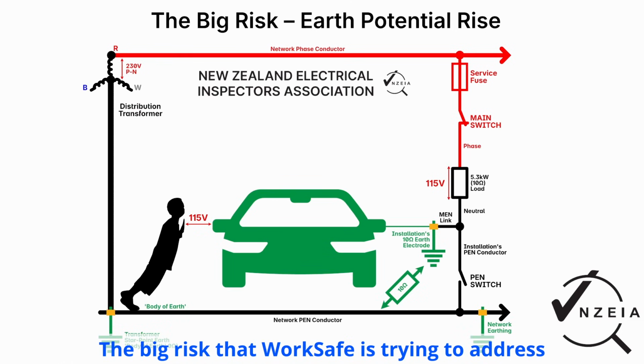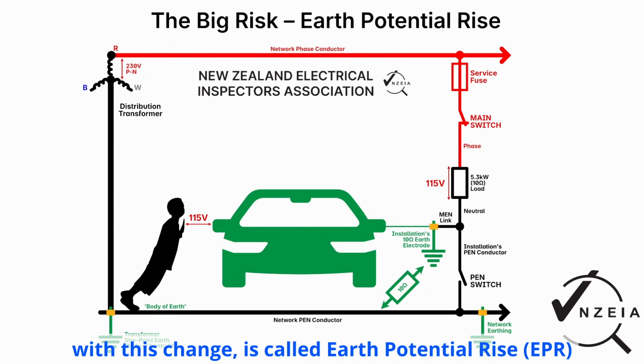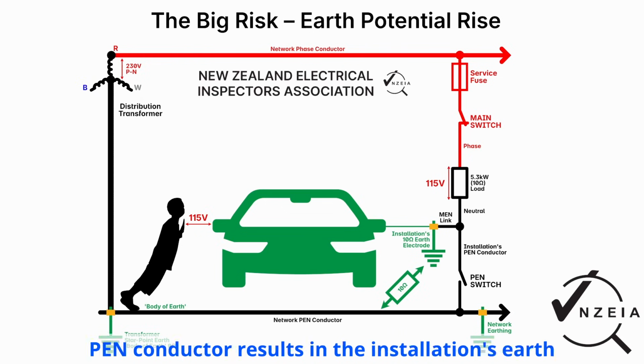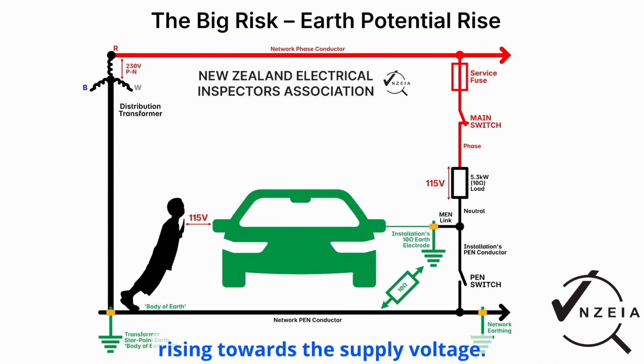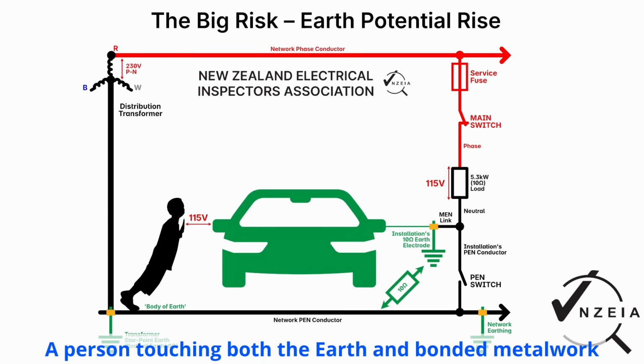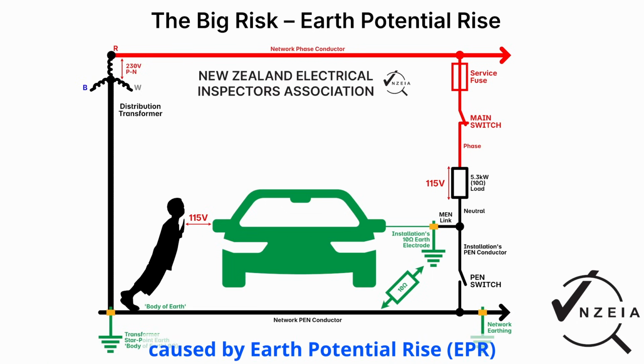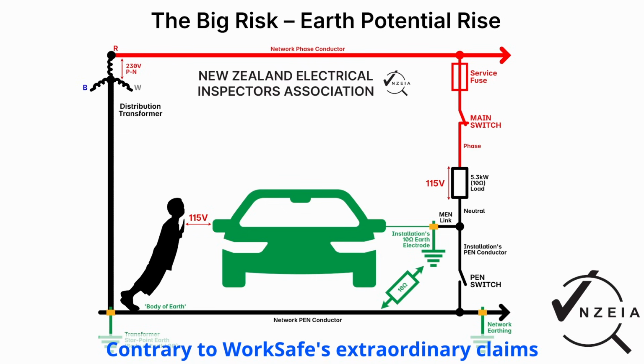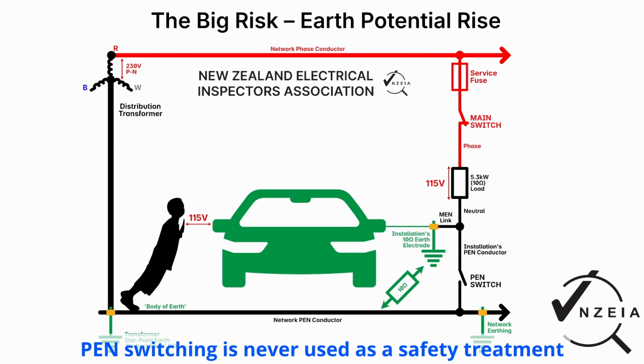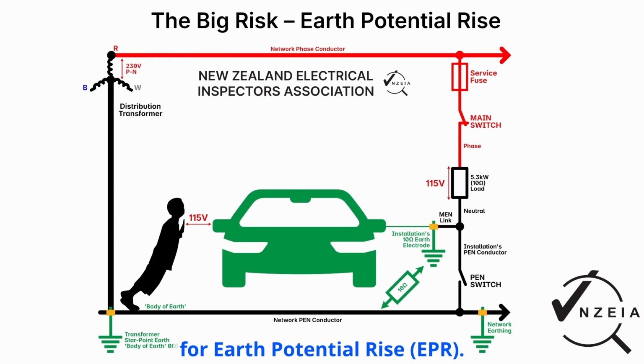The big risk that WorkSafe is trying to address with this change is called earth potential rise. A compromised or switched open-circuit PEN conductor results in the installation's earth rising in voltage towards the supply voltage. A person touching both the earth and bonded metalwork can get electric shock caused by earth potential rise. Contrary to WorkSafe's extraordinary claims, PEN switching is never used as a safety treatment for earth potential rise.